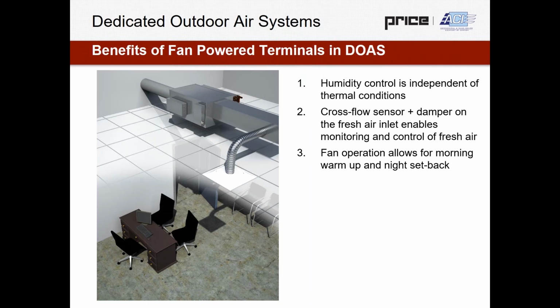Having that EC motor is also a huge advantage. So that fan is going to allow for morning warm-up and night setback, which, for instance, with a chilled beam system, you would either need some kind of inline fan system, or you would have to have the air handler running to heat the space up potentially in the morning if it was a chilled beam only system.